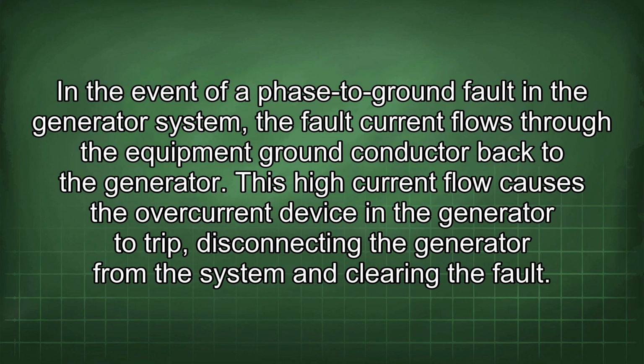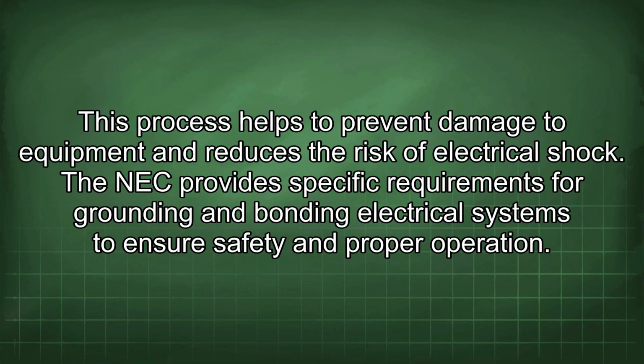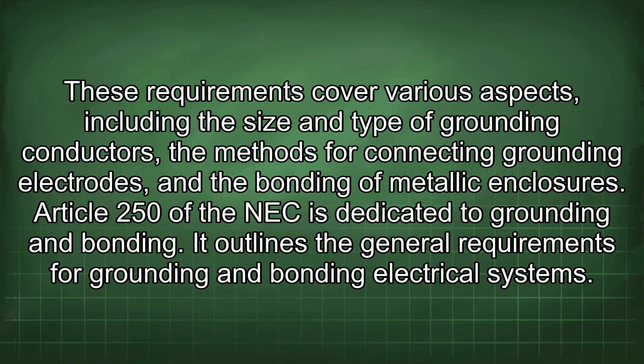In the event of a phase to ground fault in the generator system, the fault current flows through the equipment ground conductor back to the generator. This high current flow causes the overcurrent device in the generator to trip, disconnecting the generator from the system and clearing the fault. This process helps to prevent damage to equipment and reduces the risk of electrical shock. The NEC provides specific requirements for grounding and bonding electrical systems to ensure safety and proper operation. These requirements cover various aspects, including the size and type of grounding conductors, the methods for connecting grounding electrodes, and the bonding of metallic enclosures.